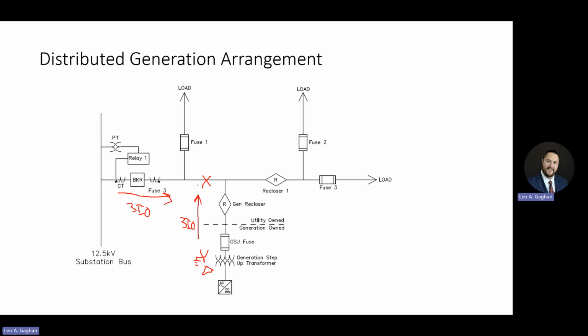Now, because of this ground source, the total fault magnitude going into the X has increased, right? But we've now created a current divider. Some of it went through this winding, and let's just say at this station, we had delta Y. Some of it will be sourced from this Y winding. Well, that current divider has actually pulled some of that magnitude away from this source. And although the total fault current has increased into that X, the amount of fault current that went through this breaker has gone down, which means we may need to reevaluate the sensitivity of that ground overcurrent element. So that's a consideration.